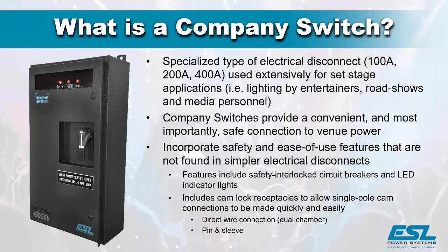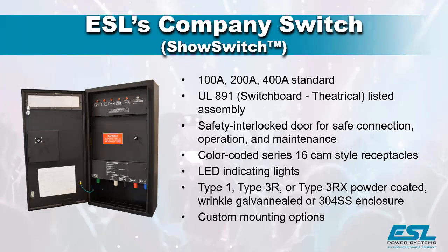We'll also talk about the pin and sleeve when we get to that part. Just to give you more detail, looking inside the company switch, you can see it's got dead front construction across the front, plenty of warning labels and things like that. We do everything following all the correct standards, these are built to UL 891. They're completely safe. You can see in the center where the interlock handle pops through the dead front, so when you open the door, the handle on the front will kill the breaker. Every time you open the door, the unit is dead, and that's kind of the raison d'etre for these things, it's very safe that way.